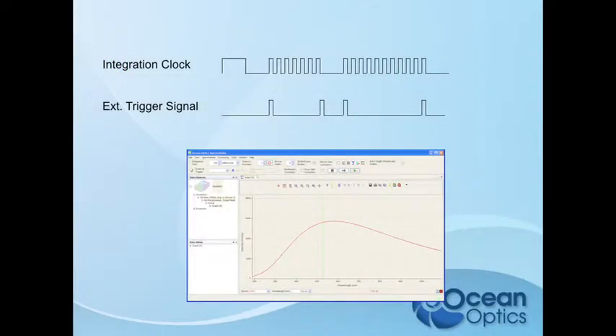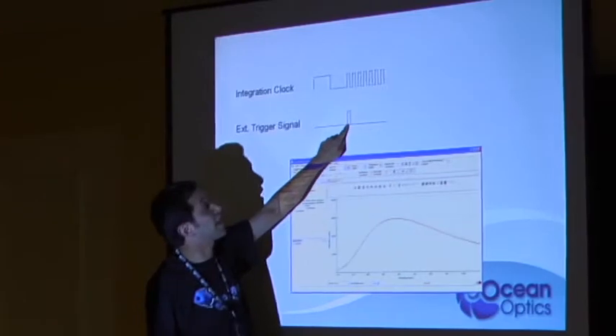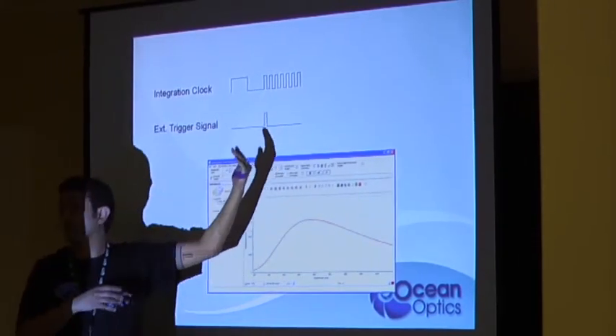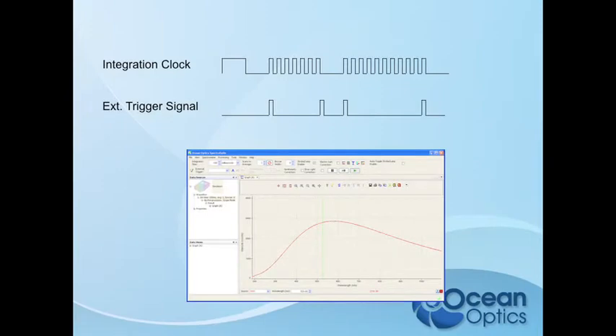That's the synchronization trigger. You use this when you have a chopper, for example, or when you have an unknown integration time and you don't know how long you'll need to be reading. It will synchronize the frequency of the event with your integration time. Like the external hardware trigger, it requires a rising edge signal — a 0 to 5 volt transition. It will synchronize the integration time to the frequency of the trigger pulse. This is specific to the Maya and any Hamamatsu detectors.